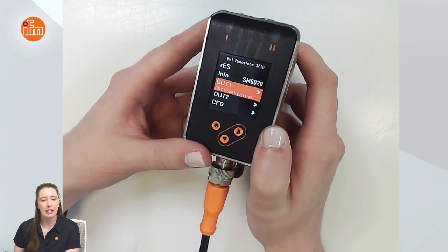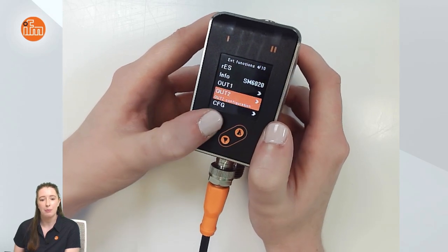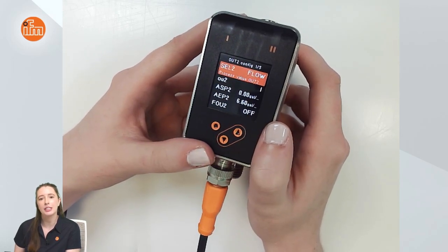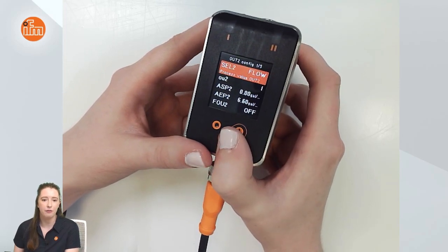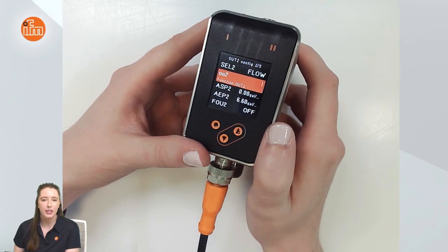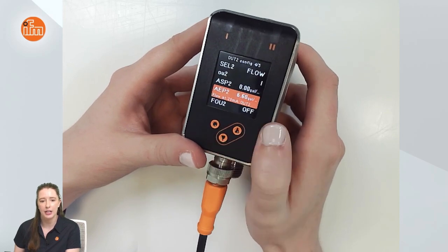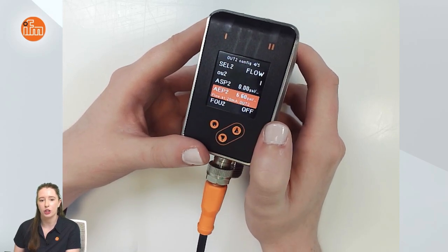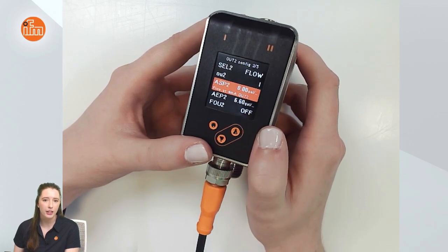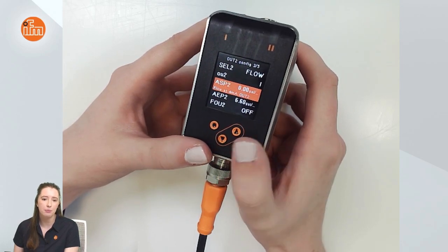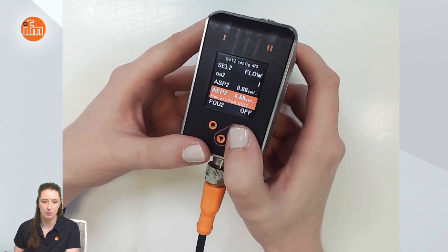Going back into the extended functions menu and down to the output 2 menu, you can see all of the parameters specific for output 2. It is factory set for flow and the output is set for I, which is the analog output, which is why you see ASP2 and AEP2 as your parameter sets. ASP2 is your analog start point, which represents your 4 milliamps, and AEP2 is the analog endpoint, which represents your 20 milliamps.